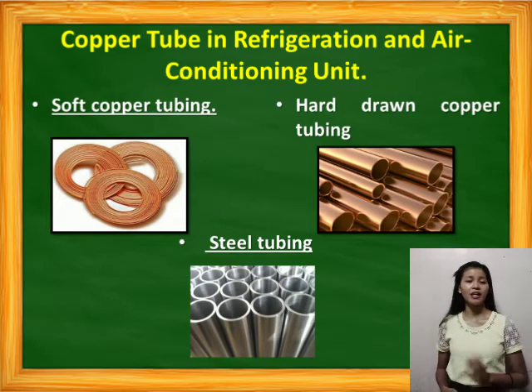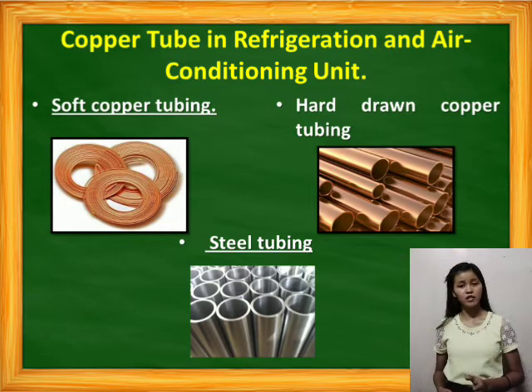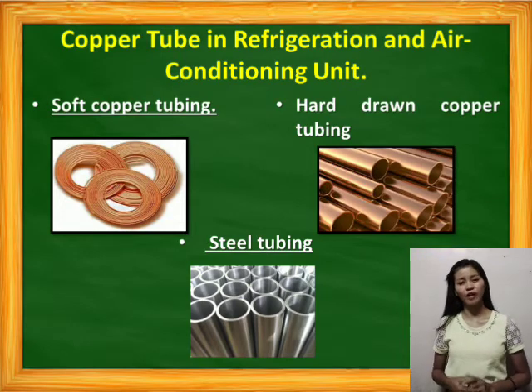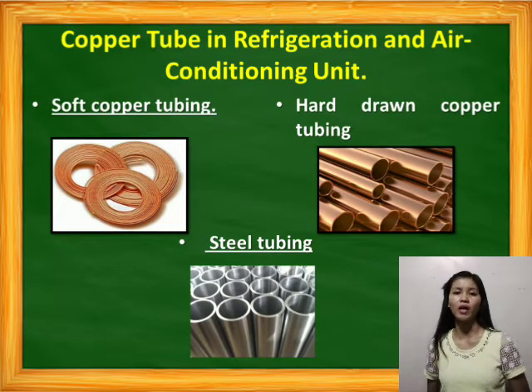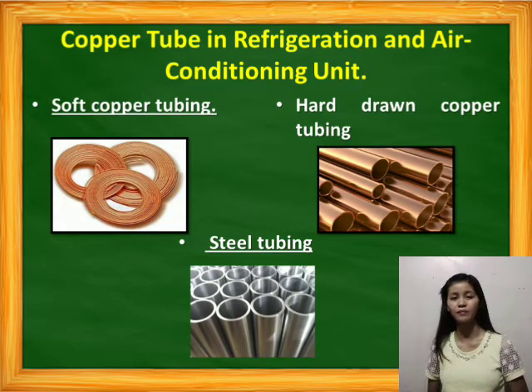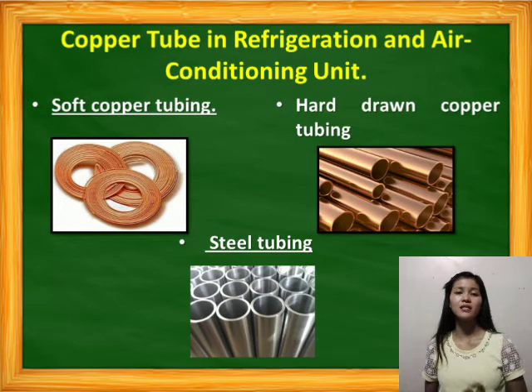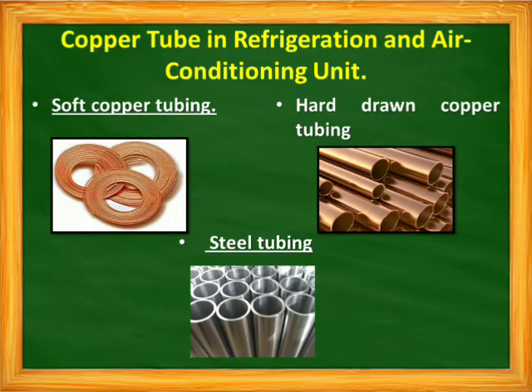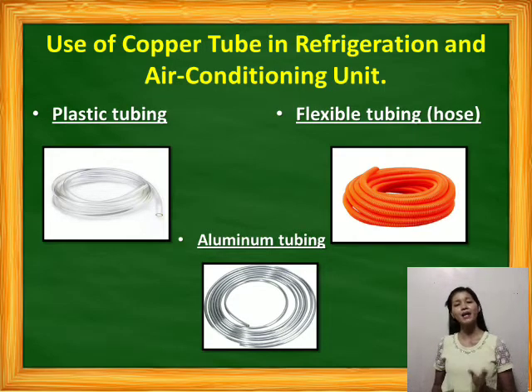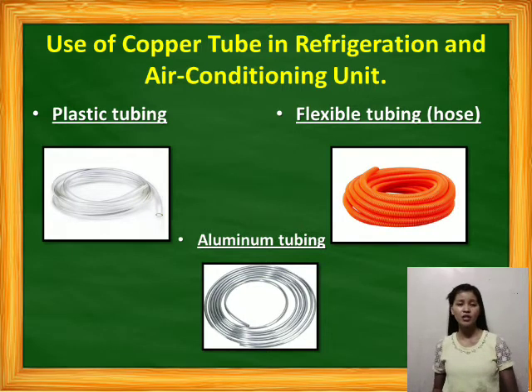Copper tubing in refrigeration and air conditioning: copper tubing is the most important material specifically for refrigeration piping circuits. The first type is soft copper — it is used for commercial refrigeration and air conditioning works because it is easy to bend. Second is hard-drawn copper tubing, used in commercial refrigeration and air conditioning applications. Next is steel tubing, a thick wall tubing used in refrigeration and air conditioning work, with size practically the same as copper tubing. Next is plastic tubing, which has the most common substances used for manufacturing. Then flexible tubing, commonly used in suction lines in many refrigeration systems and in commercial air conditioning applications.